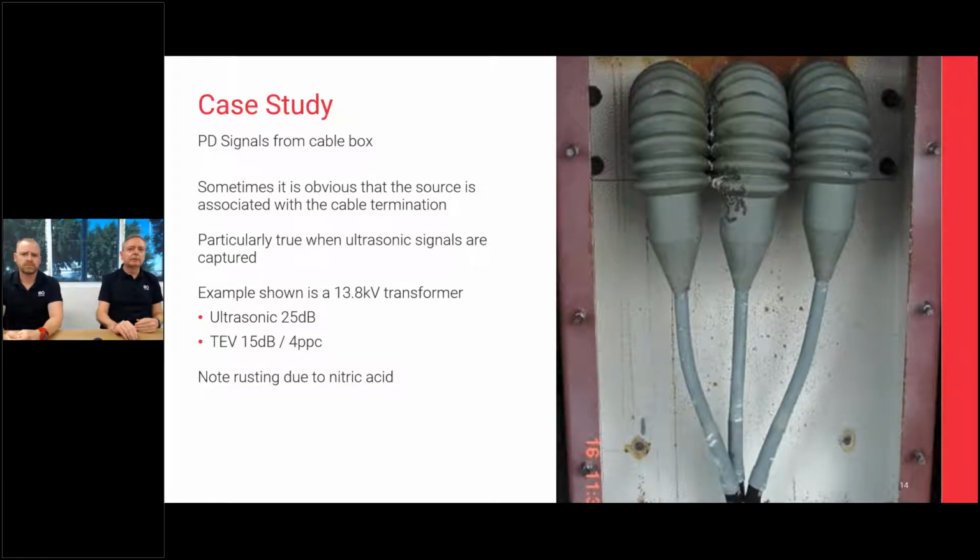I just saw a new example of a very similar case, using the incorrect boots inside a termination, just last week. So that one's pretty obvious. It's a termination, we need to change it.